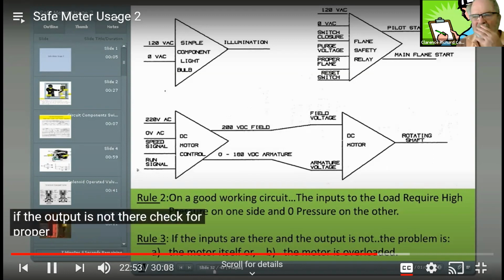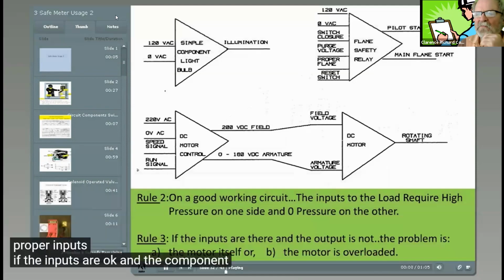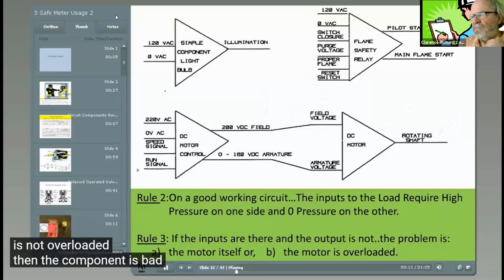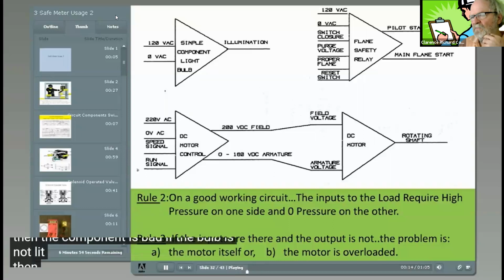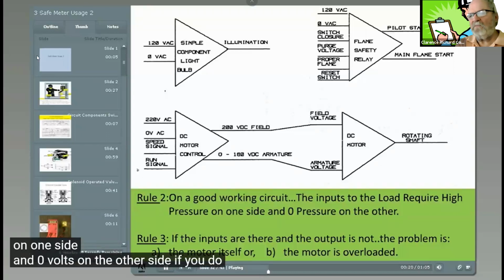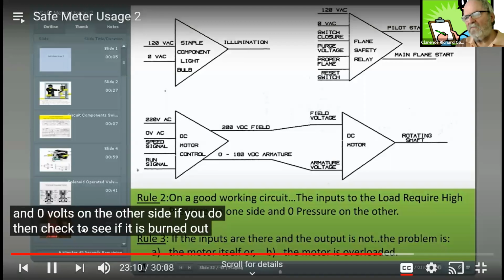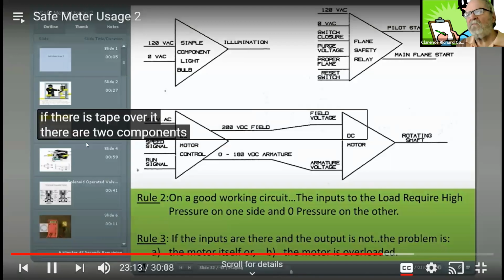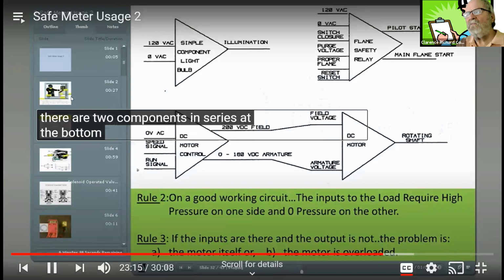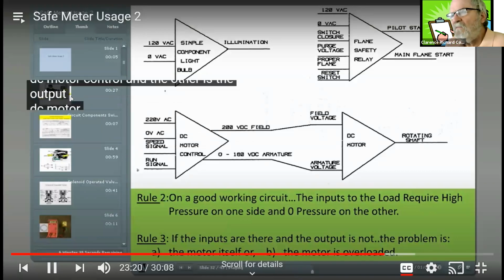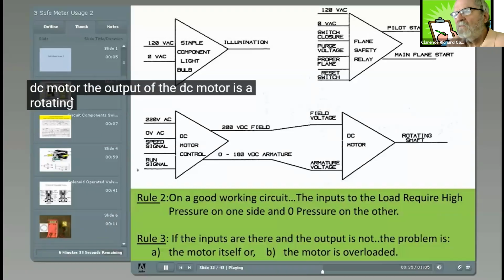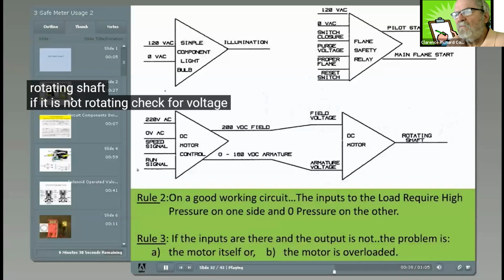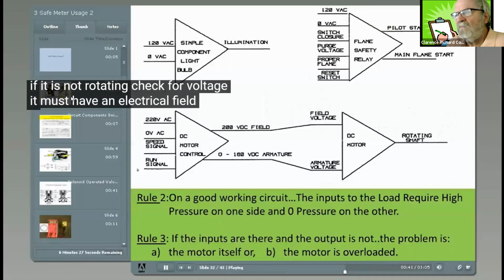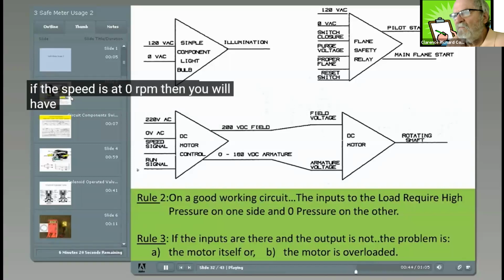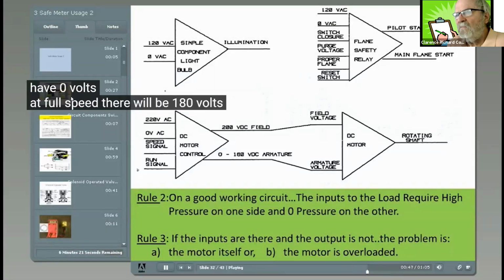If the output is not there, check for proper inputs. If the inputs are okay and the component is not overloaded, then the component is bad. If the bulb is not lit, then check to see if you have 120 volts on one side and 0 volts on the other side. If you do, then check to see if it is burned out or if there is tape over it. There are two components in series at the bottom. One is the input, DC motor control, and the other is the output, DC motor. The output of the DC motor is a rotating shaft. If it is not rotating, check for voltage. It must have an electrical field. If the speed is at 0 RPM, then you will have 0 volts. At full speed, there will be 180 volts.